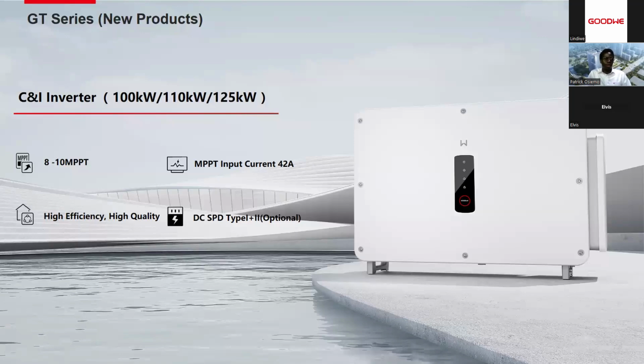So I will continue. As I was mentioning, this is the GT series implemented in our C&I space in the sizes of 100, 110, and 125 kilowatts. Some of the features that we will be going through are that it has between 8 and 10 MPPTs with 2 strings per MPPT. Each MPPT can handle a current of 42 amps. Then there is very high efficiency and quality compared to our older product, which is the HT. We'll also be comparing the new inverter, the GT, versus the HT. We also have integrated SPDs, both on the DC and AC side. As you can see, that's how the GT inverter looks.